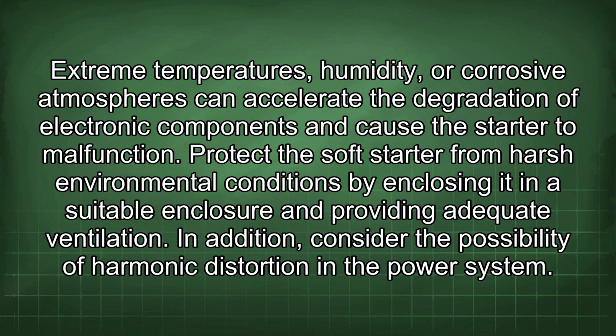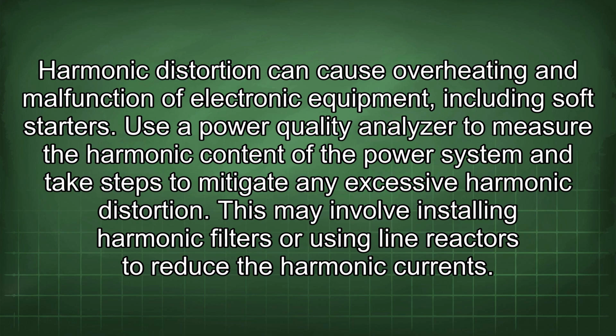In addition, consider the possibility of harmonic distortion in the power system. Harmonic distortion can cause overheating and malfunction of electronic equipment, including soft starters. Use a power quality analyzer to measure the harmonic content of the power system and take steps to mitigate any excessive harmonic distortion. This may involve installing harmonic filters or using line reactors to reduce the harmonic currents.